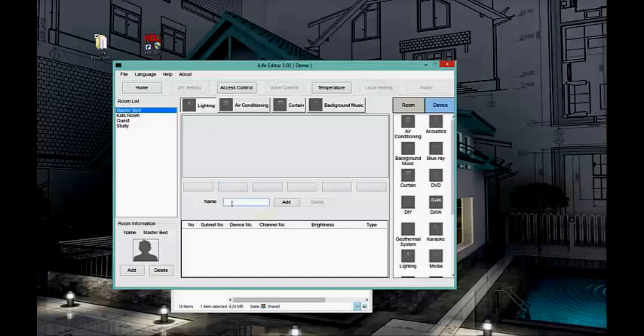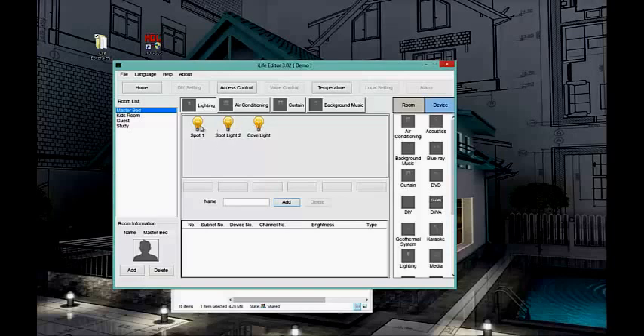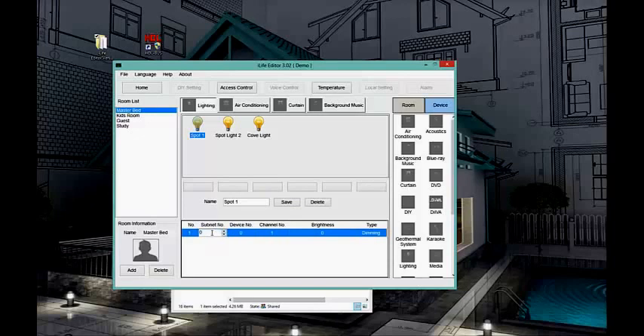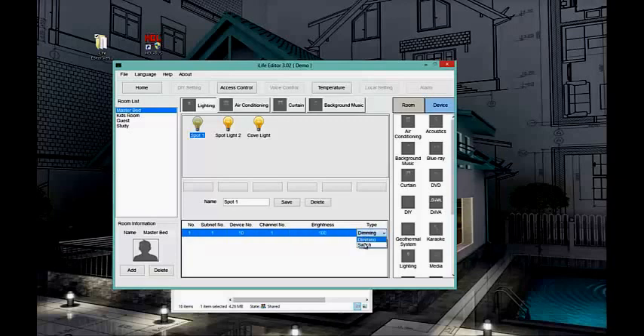Let us start programming lighting. To program lighting is very simple — we just add a couple of lights. I have Spotlight 1, Spotlight 2, and Cove Light. Now I have created three channel lights. I click on Spotlight and I have to define the address of my dimmer — it's module 1, channel number one, at 100 percent. For the type of load: if it is connected to a dimmer you select 'Dimmer'; if connected to an on/off relay you use 'Switch.' I'll add it as a dimmer and save.